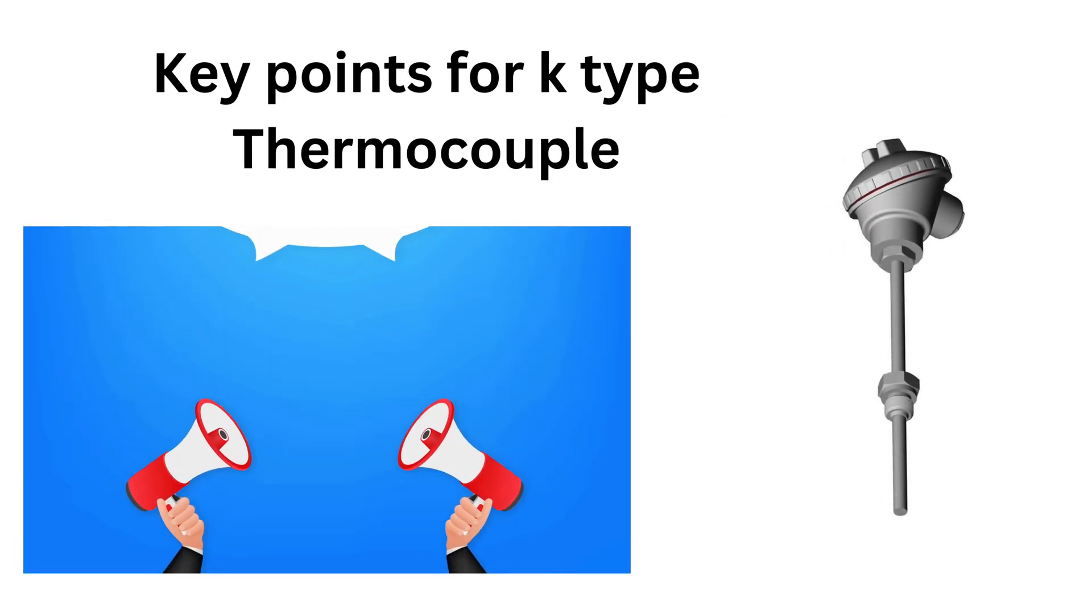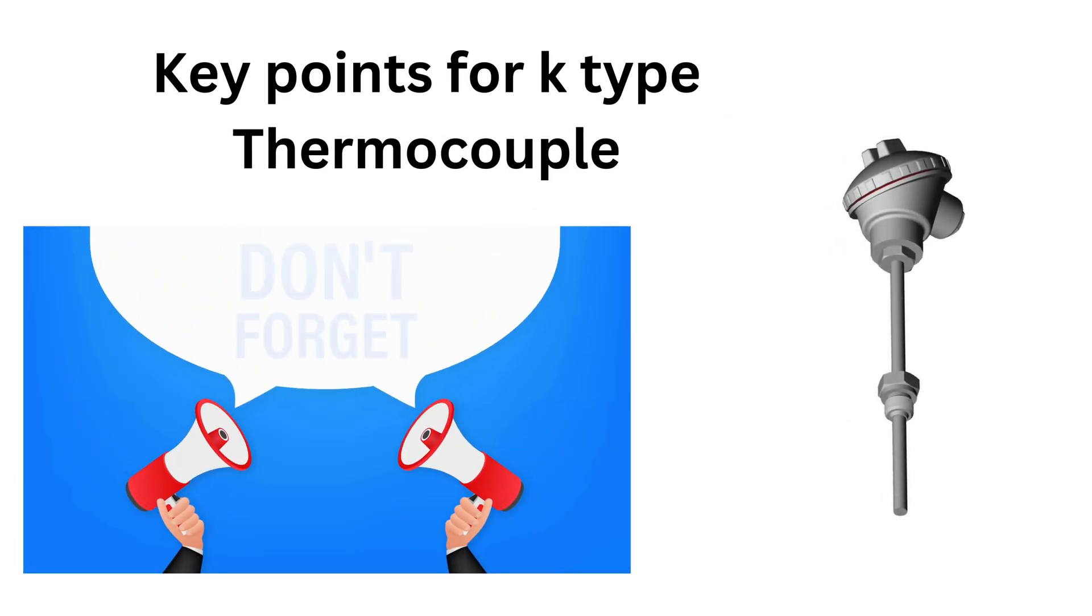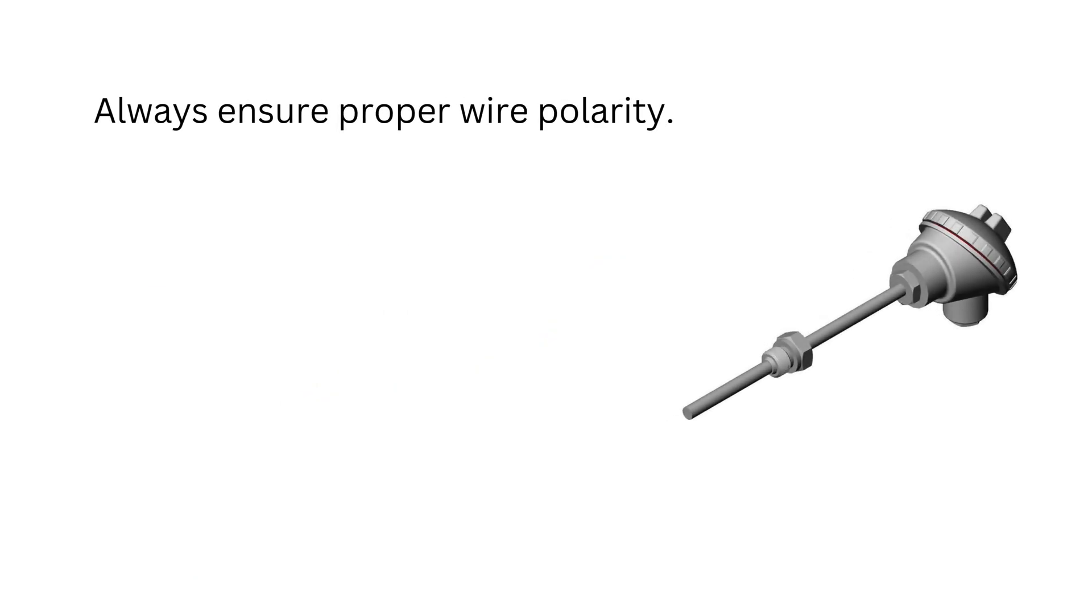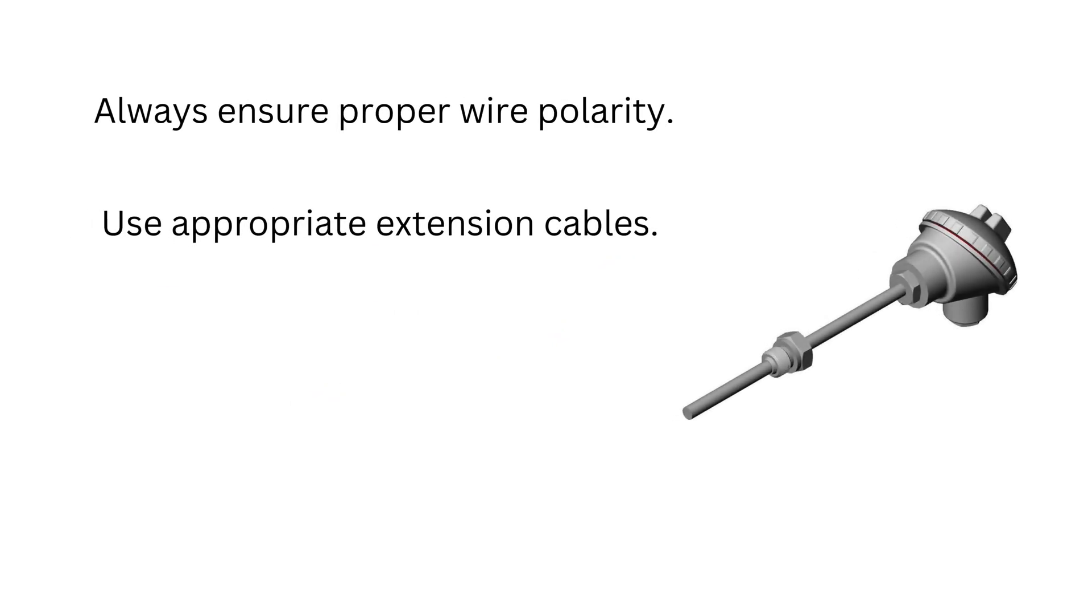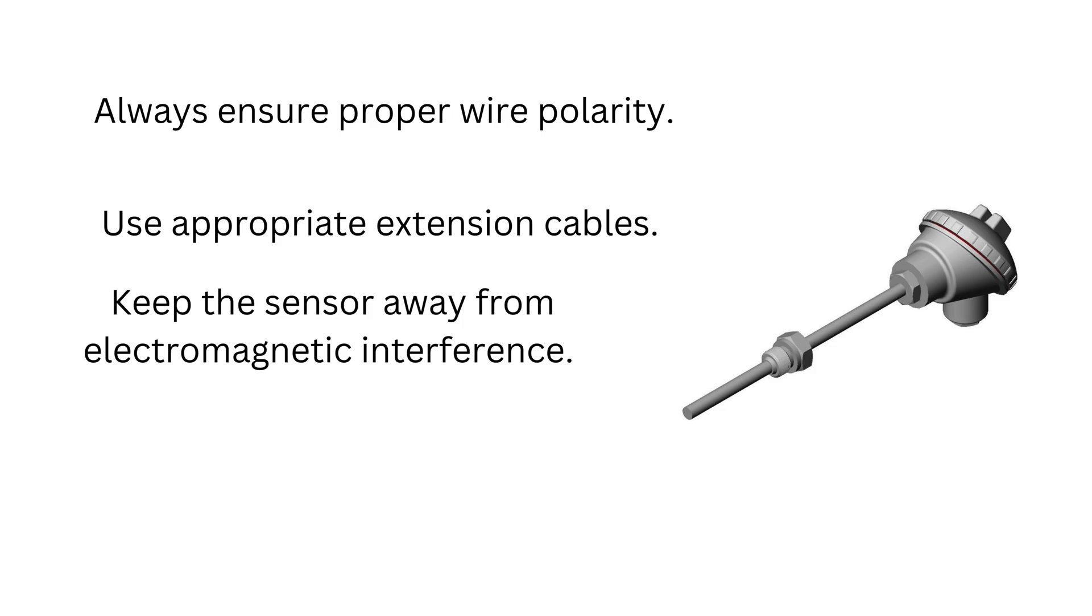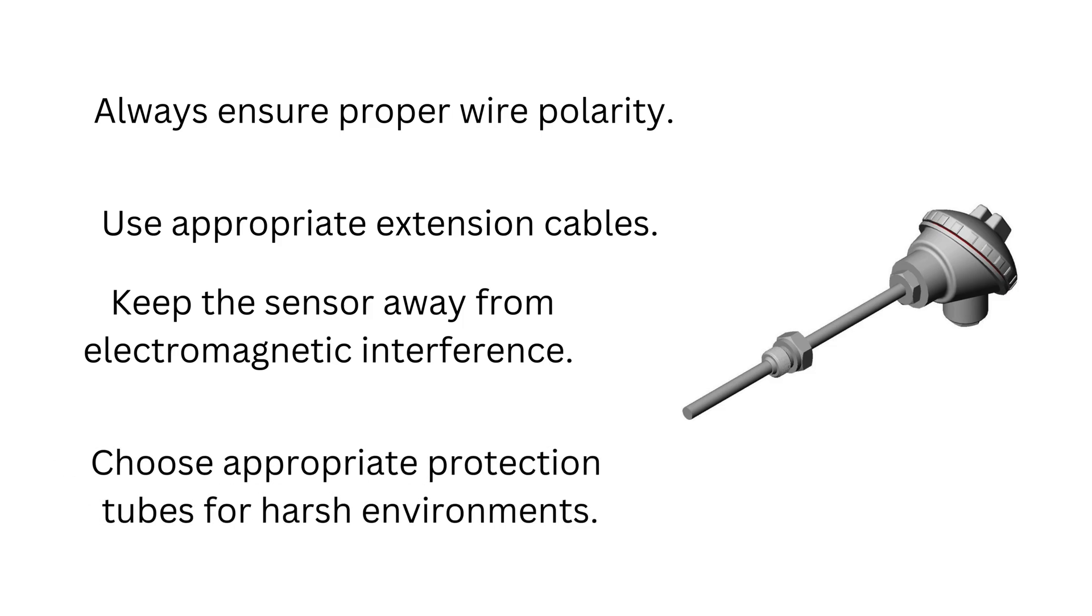Remember these key points for K-type thermocouple. Always ensure proper wire polarity. Use appropriate extension cables. Keep the sensor away from electromagnetic interference. Choose appropriate protection tubes for harsh environments.